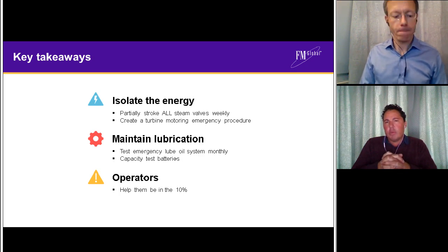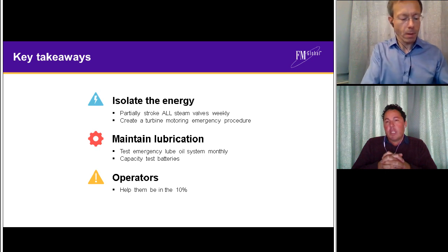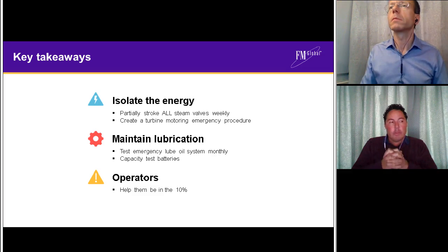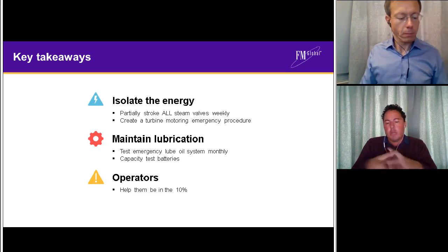My initial response is yes, in the sense that you have your emergency stop valves and your isolation valves on the steam system, and on the oil system there are generally isolation valves, but you'd like to manage those very carefully, right? You need to make sure that those valves are key controlled, as you would any critical safety valve, to ensure that there's no chance of your turbine being starved of oil.